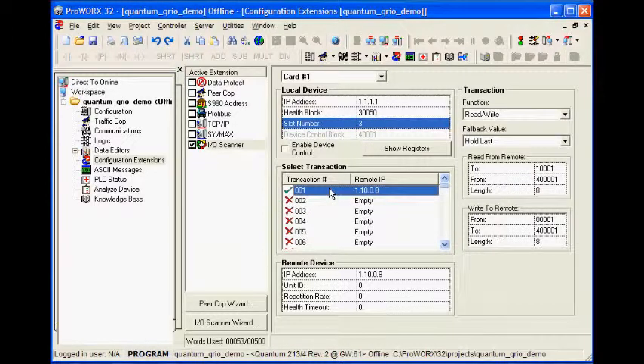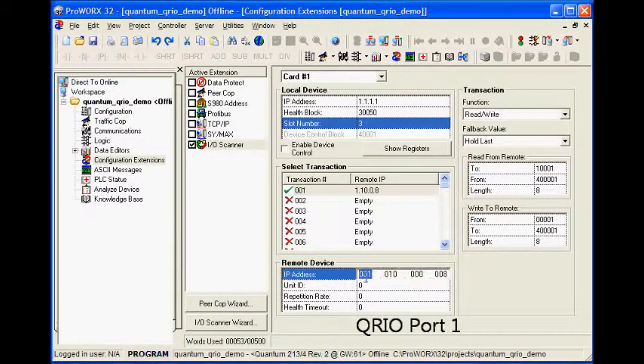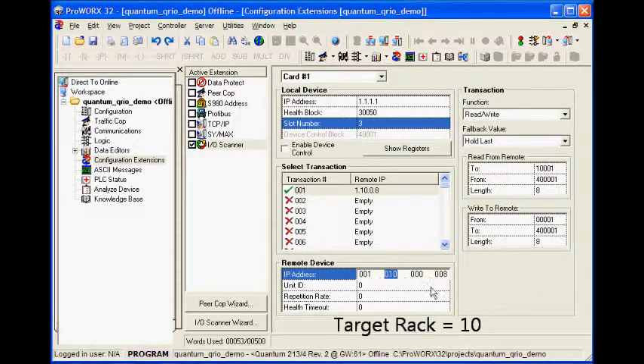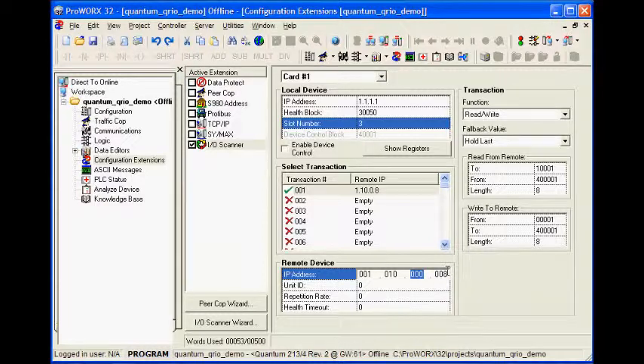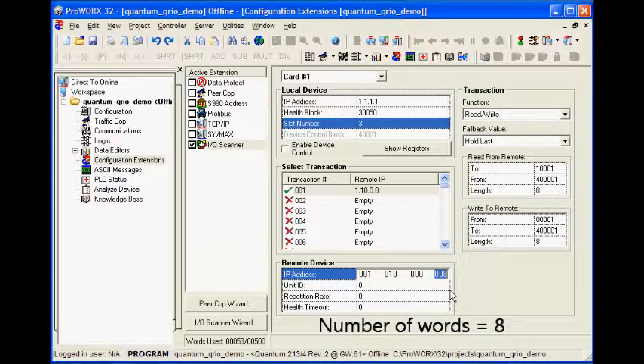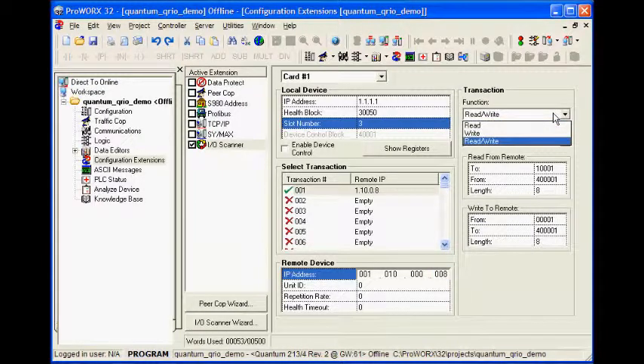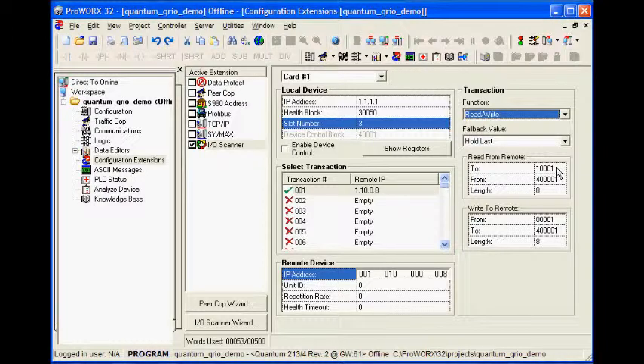Each logical remote rack is defined by an entry in the I/O scanner table. The entry's IP address selects the QRIO port, rack number, group number, and number of words in the rack. This rack contains both inputs and outputs, so the function is set to read-write. The fallback value may be set to 0 or hold last value.